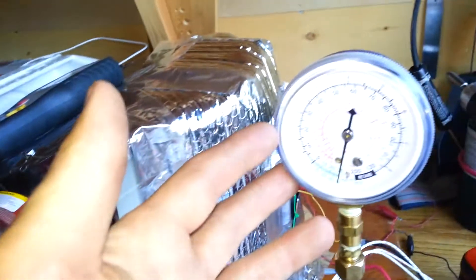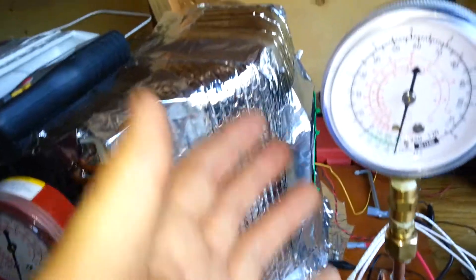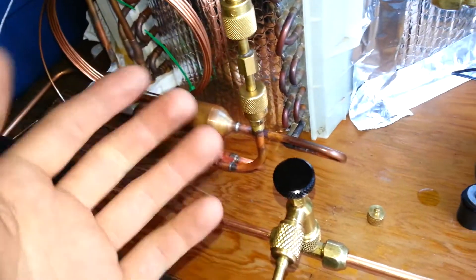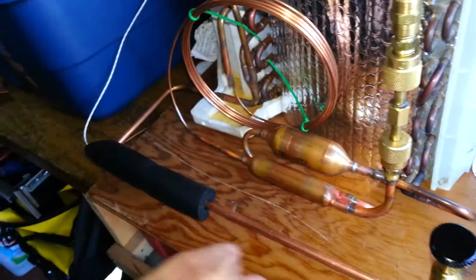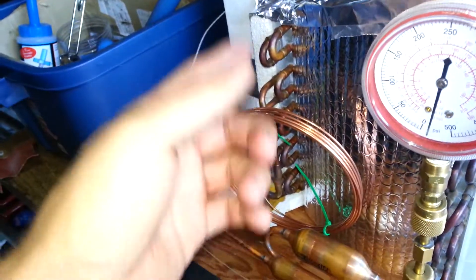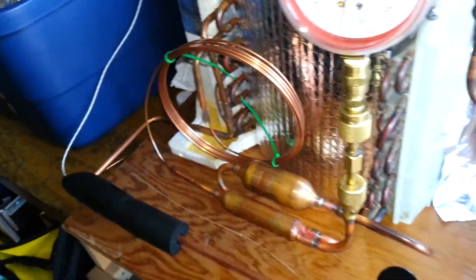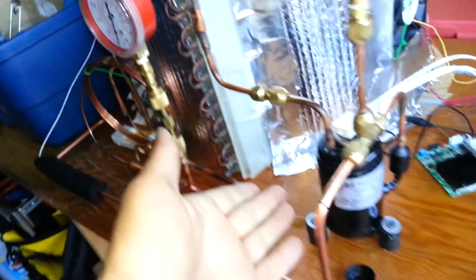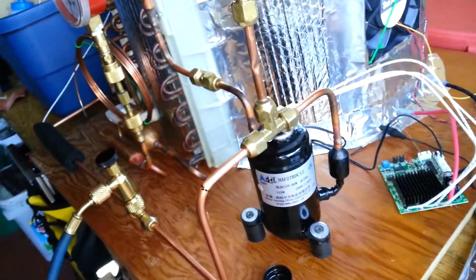Right now, it pulls the low side down really quite well. Very, very fast. But to do an evacuation on the high side there, it's pulling through the evaporator and it's pulling through the cap tube. So that's not any good. It's not going to be able to pull back through the compressor necessarily.